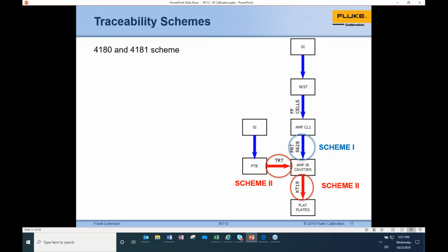One thing not shown here in the scheme is we actually kind of have a scheme 3. We have a check standard as part of our scheme 2 process. We have a gun that we calibrate using our IR process that we then send out to an independent national lab for them to check, and it comes back to us and we compare the results. So again, depending upon where you need to be in the process, whether it's a more industrial process or a lab process, it kind of depends on what you need to do within the setup for your traceability documentation.